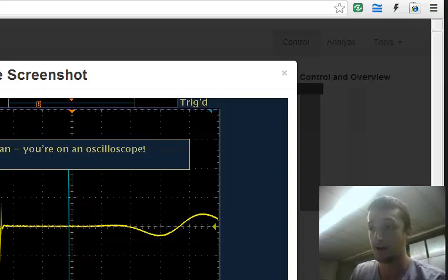I'm thinking about putting a little chart below the graph that shows wave velocity, and it'll automatically calculate the time of flight and whatnot for you. But the current setup cannot get porosity automatically because I would need a second square wave pulser, which is like $3,000.